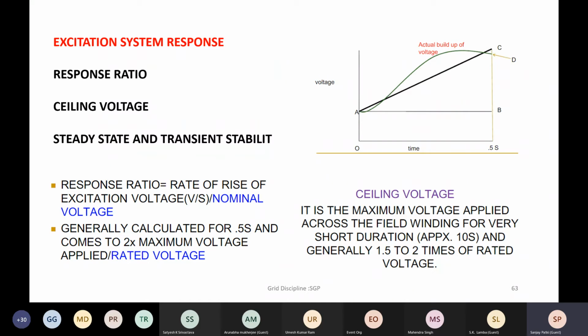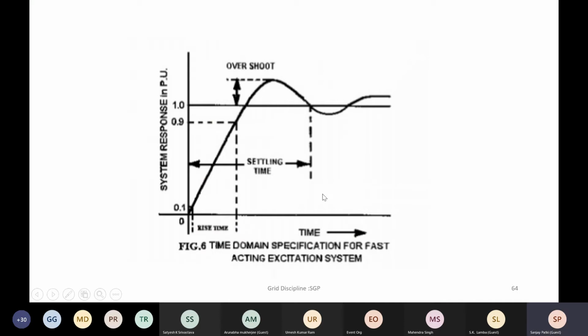From the excitation perspective, again, the response of the excitation system to the grid fault is one of the performance parameters. So when you say operation of the power station for grid condition, the ability of the generator to remain stable while it is feeding the grid fault depends on the excitation response. And these are the 3 parameters of the excitation response: the response ratio, the ceiling voltage, and steady state and transient stability condition. So this is the AVR response.